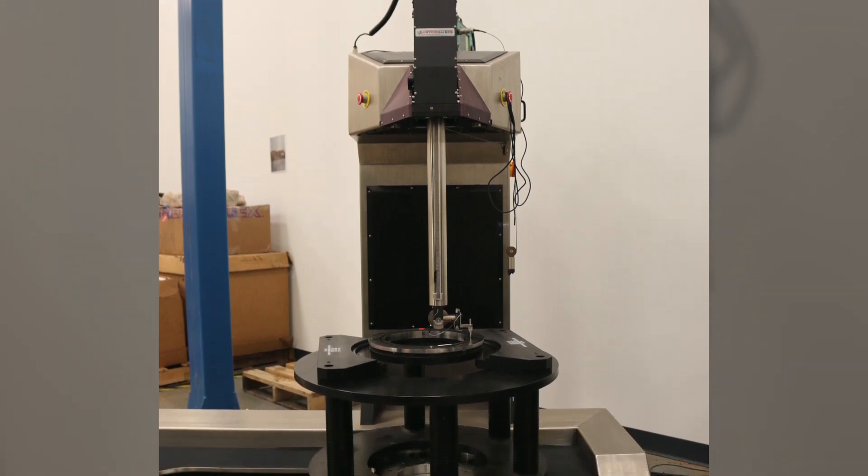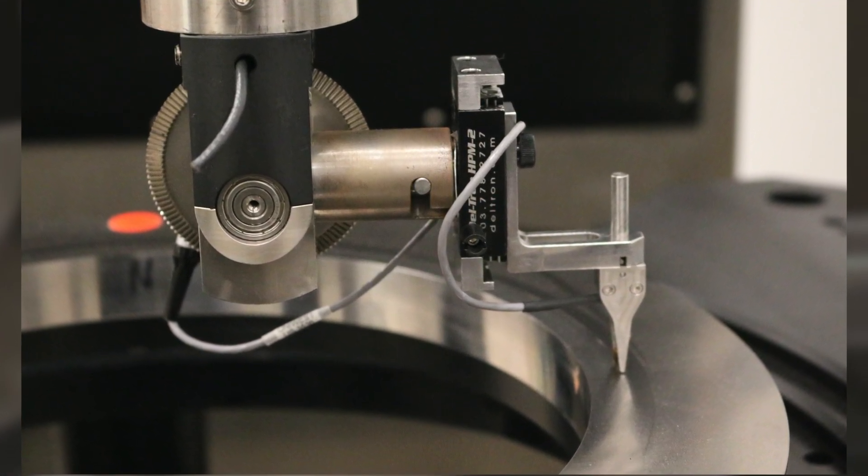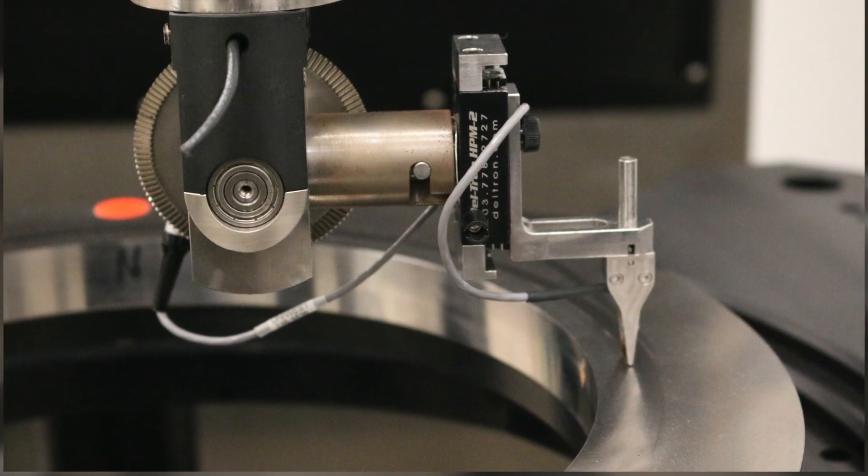Eddy Current is primarily used here at Element for the inspection of finished machine components. However, it can also be used for inspection of overhaul and repair operations and as a method of determining coating thickness.